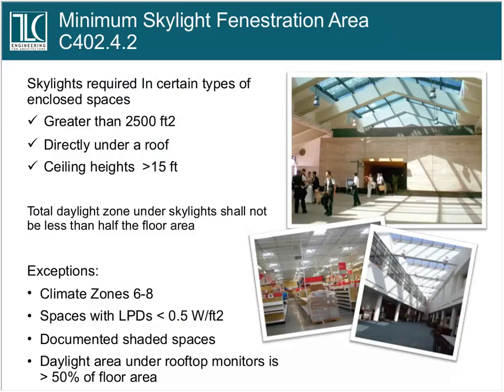I said a little bit earlier that now for the first time in the code, we're seeing requirements for skylights in certain spaces. If you have a space that's greater than 2,500 square feet, doesn't have floor-to-ceiling partitions in it, is directly under a roof, and has a relatively high ceiling height, 15 feet or greater, you need to put in skylights or roof monitors such that the daylight zone covers at least half of the floor area of that greater than 2,500 square foot space. Now, this is in a lot of space types: lobbies, assembly areas, convention centers, airport terminals, classrooms, conference rooms. This is, once again, something that we've never seen in the code, a requirement for skylights.